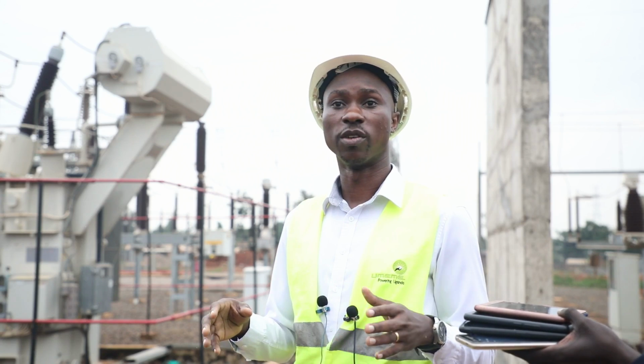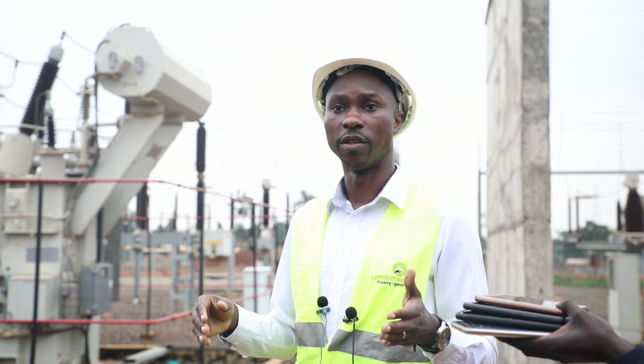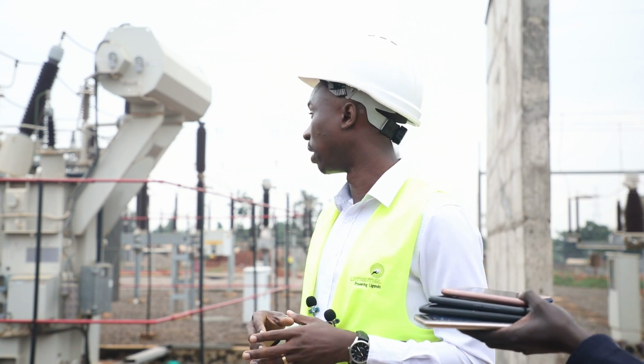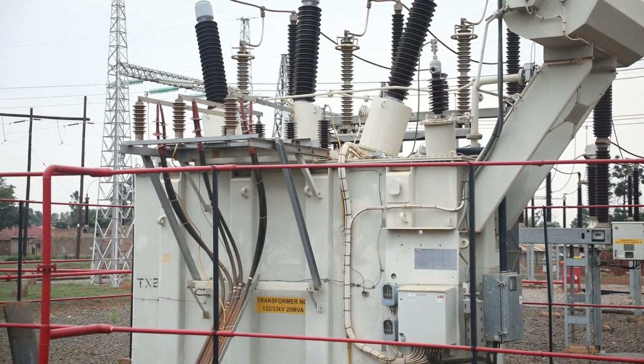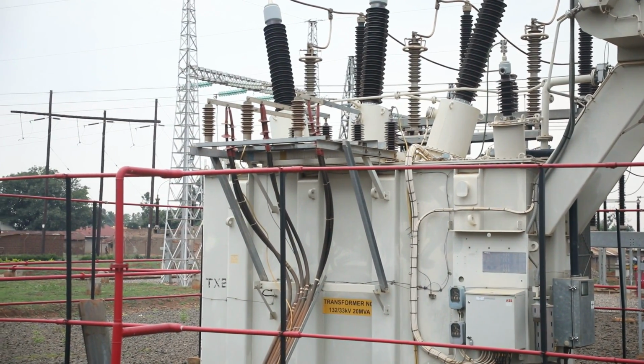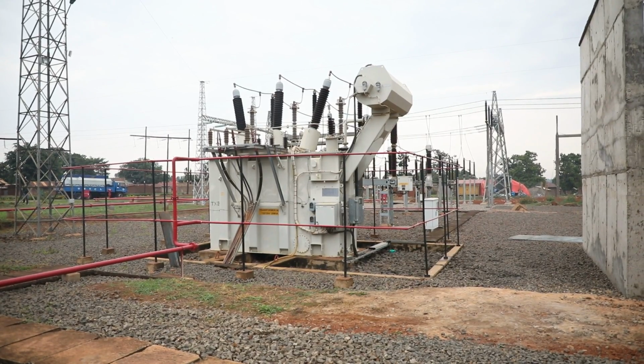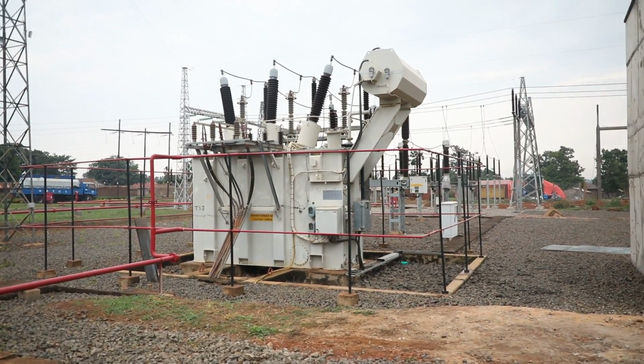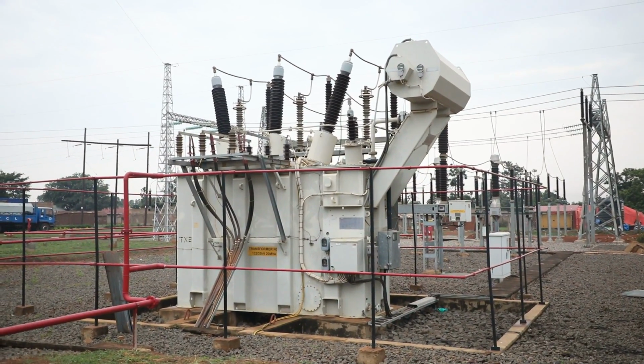The transformer that was entirely serving the northern region is rated 20 MVA, and we have a maximum demand of about 18.9 MVA.